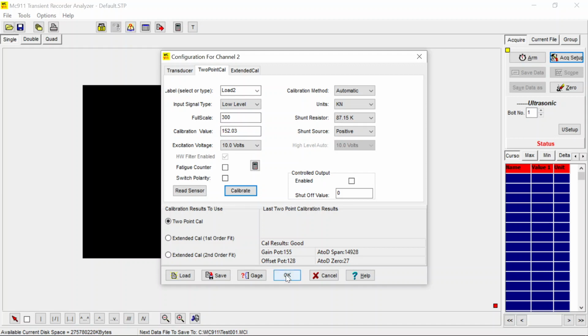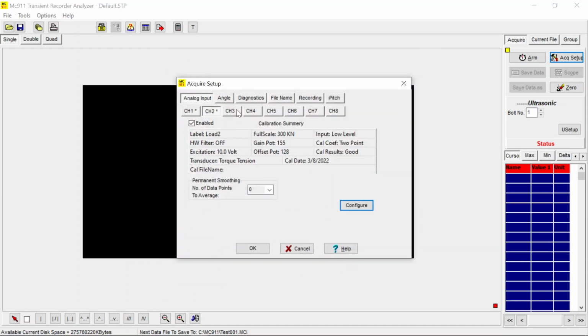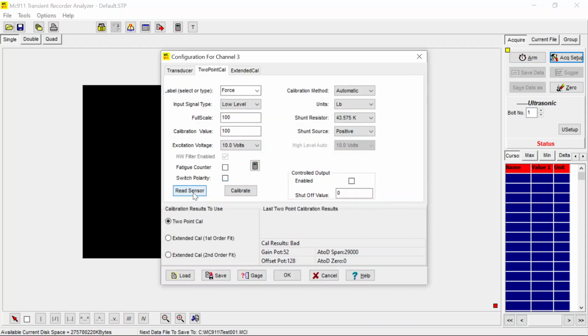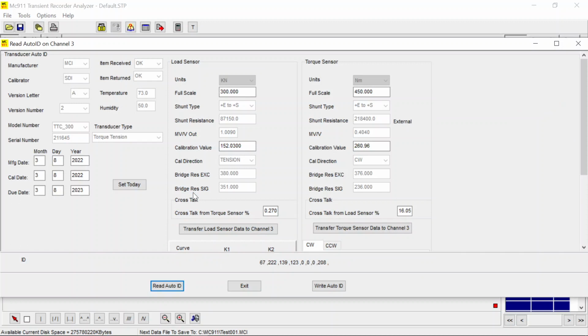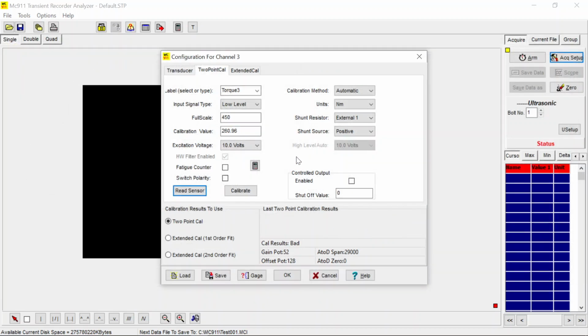So let's go to channel 3. On channel 3, we configure and read the sensor again. The same information shows up. This time we are connected to channel 3, so it's a torque transducer. So we transfer the data. As you see here, our calibration value is 260.96 Newton meter, and it requires an external one shunt resistor.